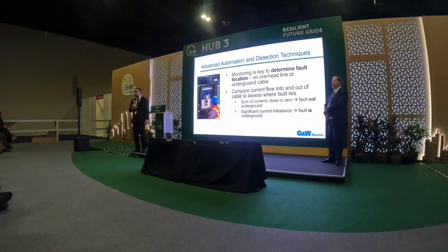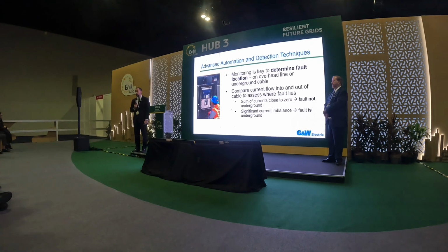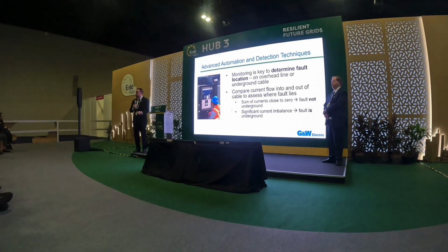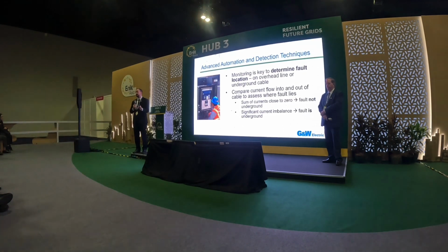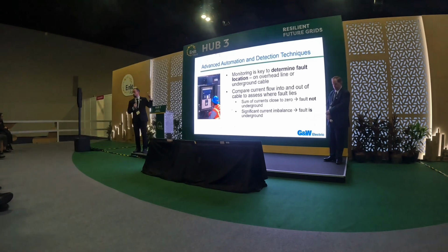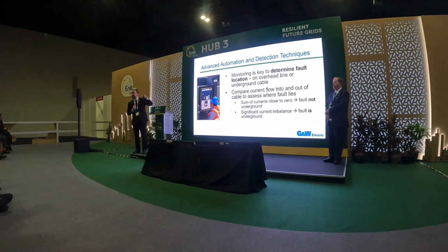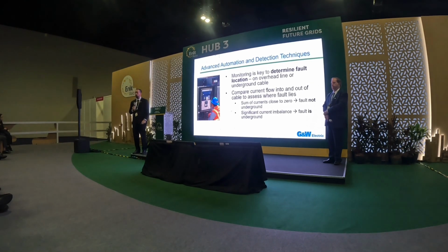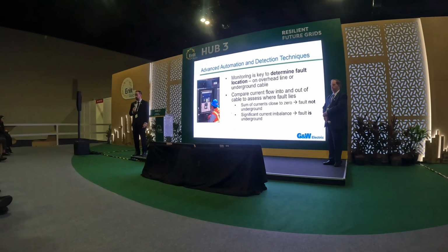And as we reviewed earlier, if it's on the underground circuit, it's likely going to be a permanent fault, and not a fault that we would want our recloser technologies that may see that same fault when it occurs to reclose back on, okay?